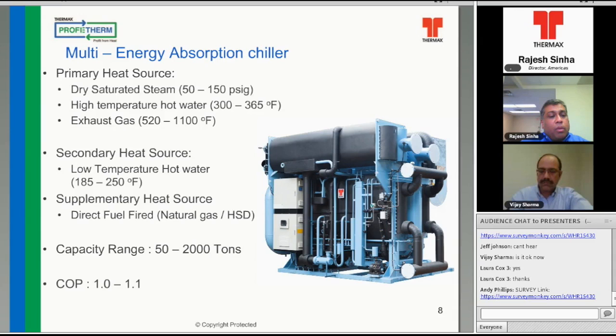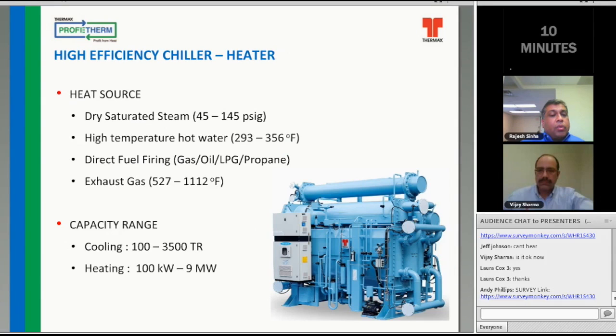And this is basically a high efficiency chiller heater. Herein, the chiller and the heating cycle both run simultaneously in the absorber, and the heat rejection happening from the chiller circuit is actually going towards the heating hot water generation. Herein, the driving heat sources could be the same: the dry saturated steam, high temperature hot water, direct fuel firing, or exhaust gases. And the capacity range could be cooling and heating 100 to 3,500 tons, 100 kilowatts to 9 megawatts.